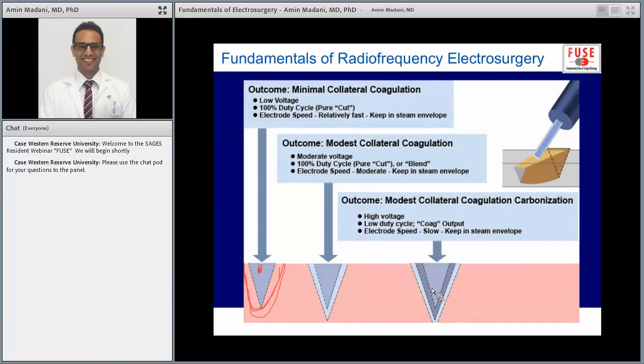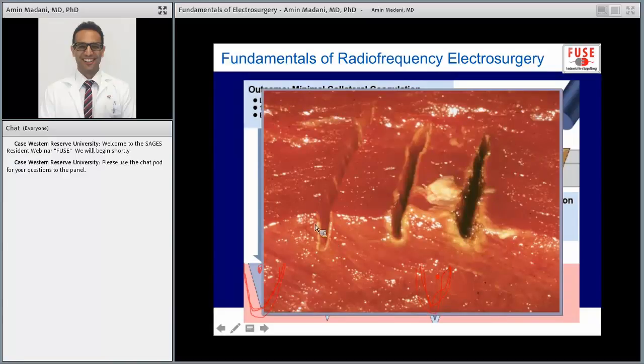When you contrast this to the one over here, where you use coag, so a high voltage, yes, you touch these tissues here, you raise the temperature, and it goes above 100 degrees Celsius, and you cut the tissue. However, because it's high voltage, this surrounding tissue here also experiences a rise in temperature. It may not be more than 100 degrees Celsius to cut it, but it will be in the 50 to 95 degrees Celsius range, where it's enough to desiccate the tissue. And so you get this coagulum that forms as well. This is demonstrated here. You have cut on one hand, with minimal desiccation of tissue, and over here you have coag, where you cut tissue, but you also desiccate the surrounding tissue. So you get collateral thermal spread.